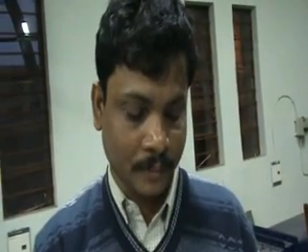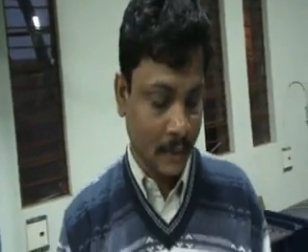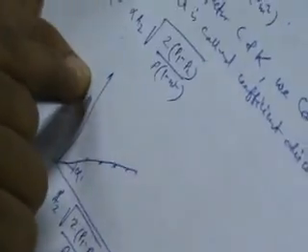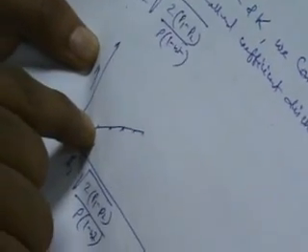Now we got the value of A2. Now the pressure drop P1 minus P2 across the orifice plate, and also we know the rho is 1.12 kg per meter cube and m equal to 0.5. Now this value we are plotting against the quantity we measure, so we get a point here. Next step, we throttle at the input so that quantity will change. So another new condition will be created. So we will measure again delta P, again quantity. So we will get another point.